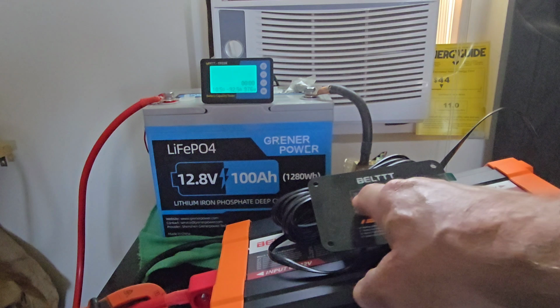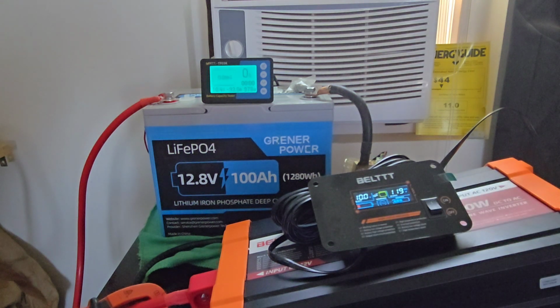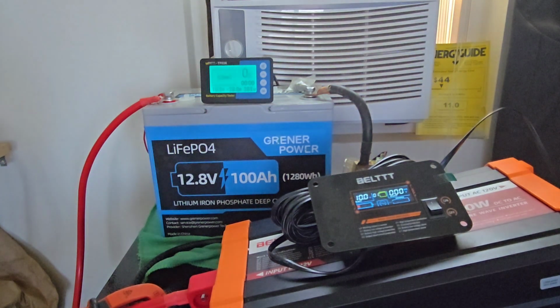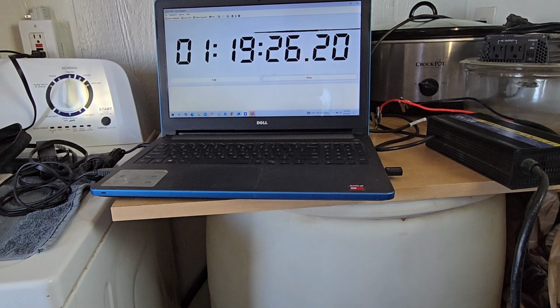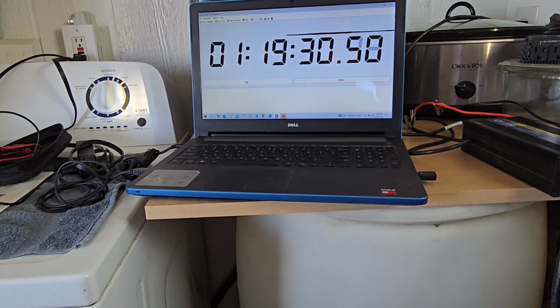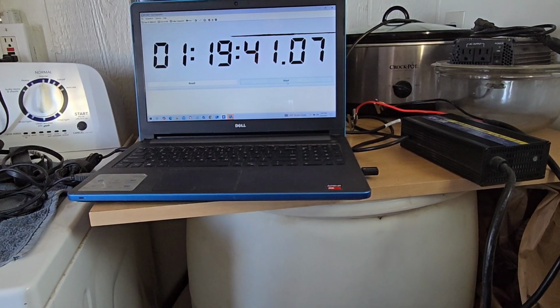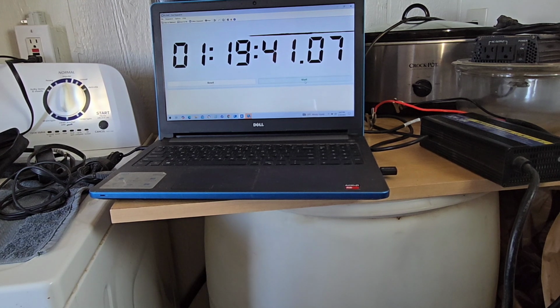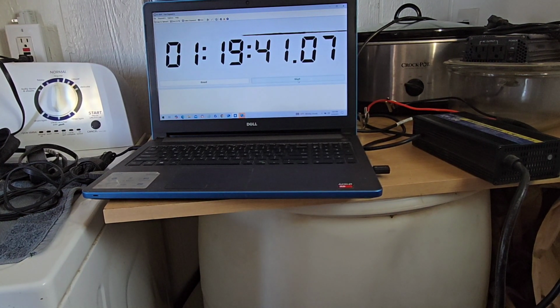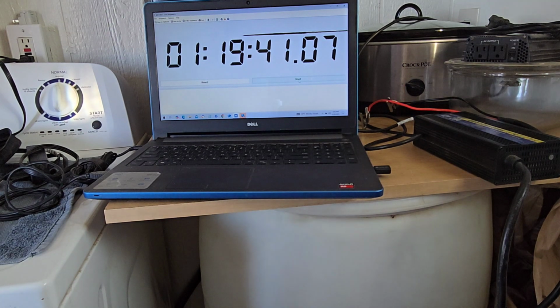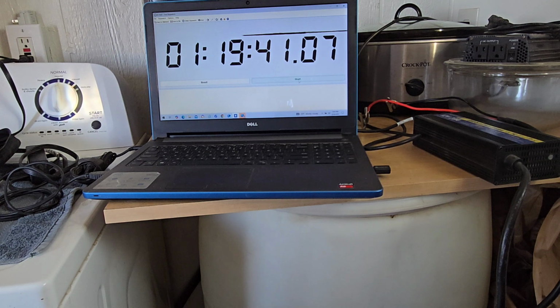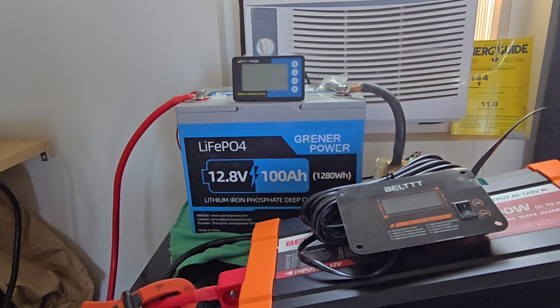And we're at 10.2 volts. When it gets to 10 volts, I'm pretty sure it's going to... oh, that's at 10 volts there. 9.9 volts now, I hear the alarm. Okay, the alarm says we're going to be shutting down here any second now. There it is, it's off. So we are just under 1 hour and 20 minutes. So it did actually meet... I'm sorry, I hit the wrong button there when I was reaching over to shut off the timer. So it's 1 hour, 19 minutes, 41 seconds. It should have been 1 hour, 19.8. It's close enough to say it did at least produce the 100 amp hours it claims to do.